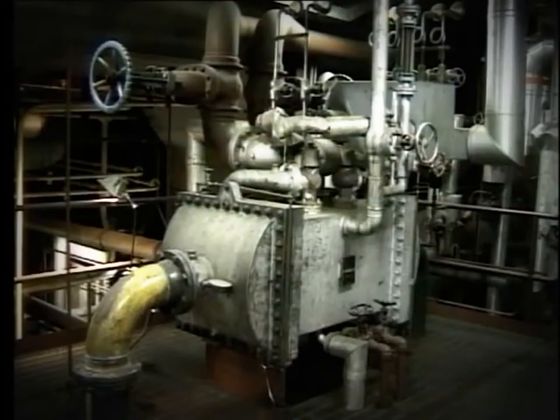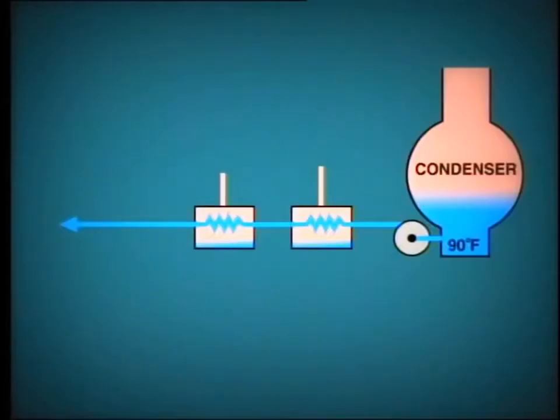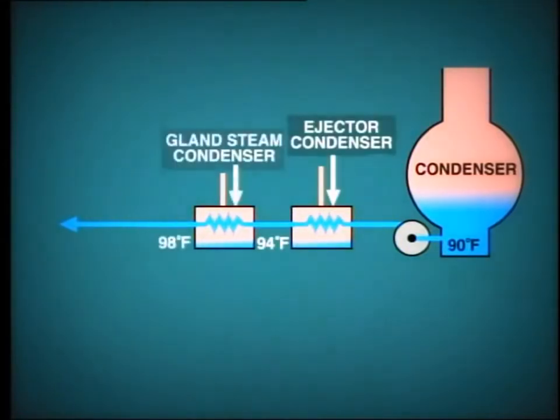Initially, a small amount of heat is picked up as the condensate passes through the steam air ejector condenser and from here through the gland steam condenser. In both cases, this heat recovery improves efficiency as it condenses ejector exhaust steam and leak-off gland steam.